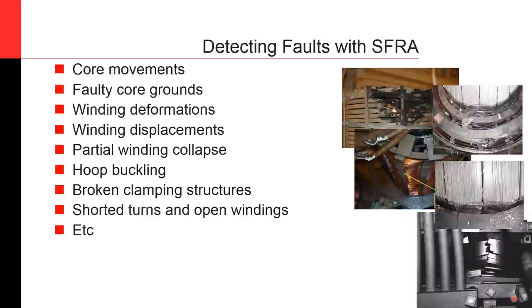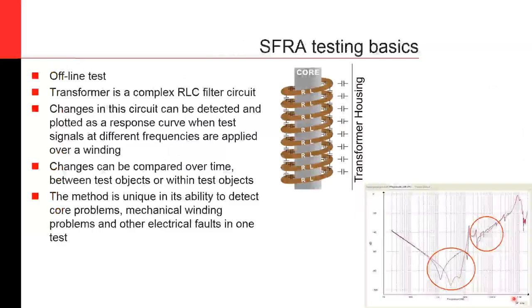SFRA is a piece of the puzzle, but it's nice because you can see a lot of information with sweep frequency response analysis. You can see core movements, faulty core grounds, winding deformations, winding displacements, winding collapse and hoop buckling — all these different things that will appear as differences in traces when looking at SFRA results. So it's one piece of equipment that gives you a variety of information about the health of your transformer.